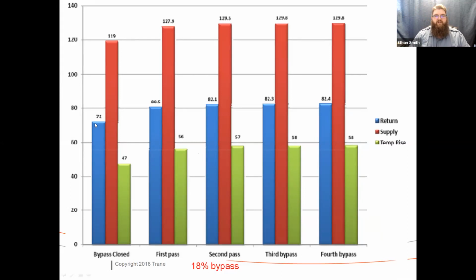Okay, we got my return temperature. This is actually a mixed return. And we have the supply temperature and the temperature rise. So with my bypass closed, we start cranking. This is an 18% bypass. This is as large of a bypass as this system would tolerate. This is an 80,000 BTU furnace.